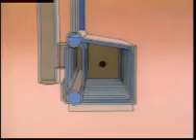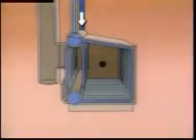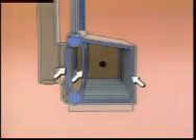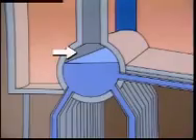The water tubes connect the drums and form a wall around the combustion area of the boiler. This is where heat is generated. Water is fed into the upper drum through a feed water inlet line. The water tubes and the lower drum are completely filled with water. The upper drum is only filled to a certain level. This provides space for steam to collect, so the upper drum is often called the steam drum.